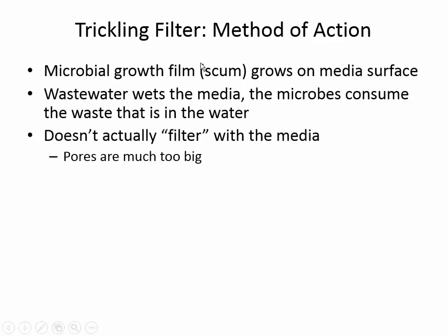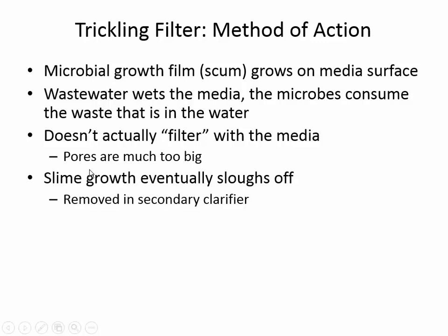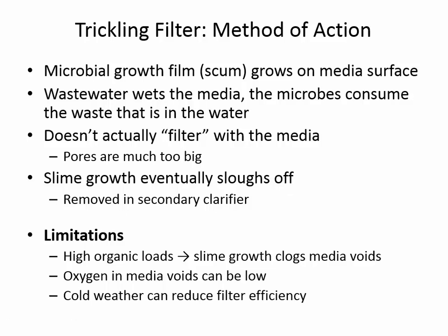Now, calling this a filter is a little bit of a misnomer, because it's not actually straining the same way that a sand filter does. Remember what the mechanism in a sand filter was: impaction and adhesion. But we still call it a filter, even though it's not really straining. Here, it's not filtering out a suspended particle, it's just a location for dissolved BOD to be removed. The slime layer eventually gets so thick that it sloughs, which means it falls off, and then it's removed in the clarifier. So this works great when it's appropriate.